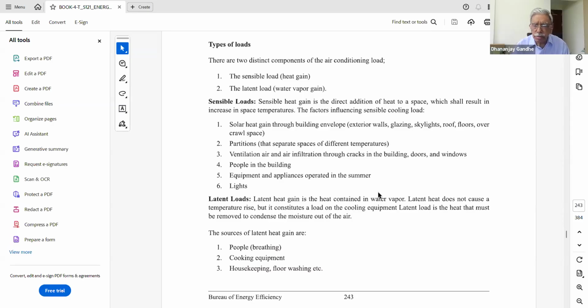Also, because the temperature is reduced, air infiltration that takes place also constitutes the sensible load. People in the building, of course, because our body temperature is a little higher. If you want to maintain a temperature of 25 or 26 degrees in the air conditioned space, the heat dissipated by the body also has to be taken into account. And then, of course, the equipment and appliances working in that particular envelope also constitute the sensible heat, and also the lights, that is, the wattage of the lamps is also the sensible load.